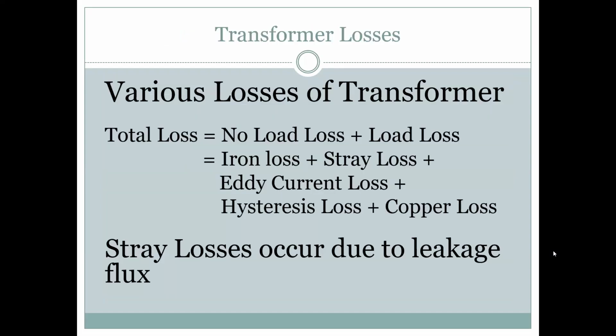Next. Now let us touch upon the losses. What are the losses a transformer incurs? Transformer loss, we always specify as the total loss. Now total loss is basically no load loss, which comes basically from the core, and load loss. No load loss is also called iron loss, because of this core, whatever the current is being passed, the iron will be consuming it, and then the iron loss will be there. Then there is the eddy current loss, because circulating current starts flowing in the core material, and that gives you the eddy current effect, and that also consumes some power.